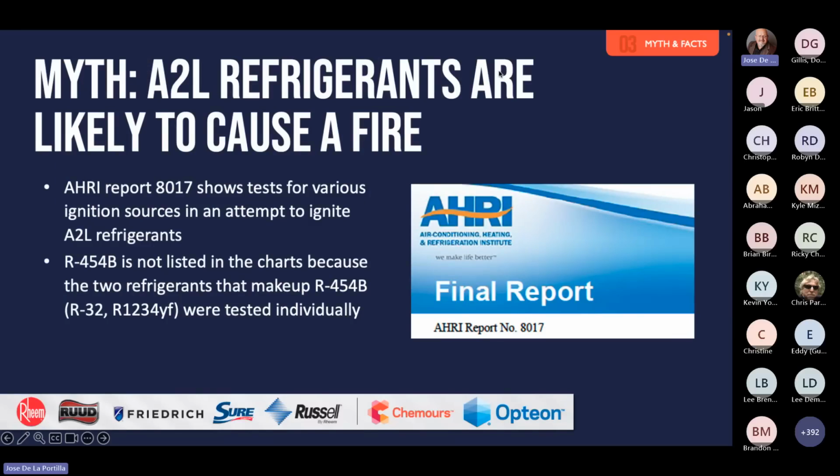Okay, so then this next myth, I'm going to walk you through a few slides. There's several of them, and you may think, okay, this is kind of getting repetitive, but I wanted to show you some really cool findings. So AHRI put out this report, the AHRI report number 8017. And what it did is they went ahead and tested the refrigerant. They created a perfect storm, right? The perfect space for ignition to take place, which we'll call stoichiometric combustion, right? They created a perfect place for that. And what they found is that through different heat sources, they couldn't get ignition to take place.